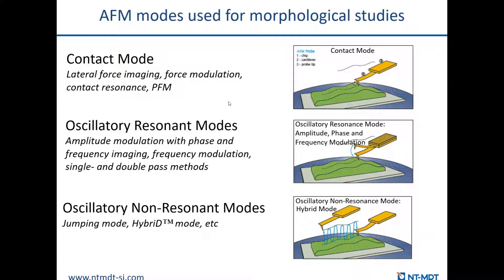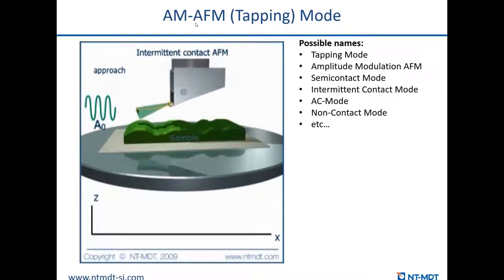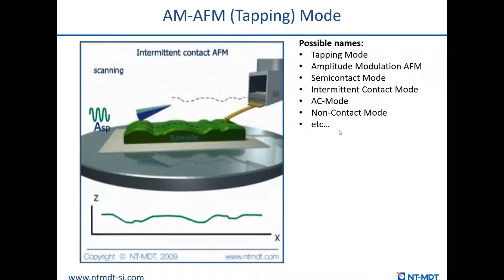There are mainly three ways of keeping interaction between the tip and the sample. First is contact mode. Second is oscillatory resonant mode, or amplitude modulation mode. Third is oscillatory non-resonance mode — we call it hybrid mode. During my talk I will mention all of them. Let's start with AM-AFM, Amplitude Modulated Atomic Force Microscopy. You may have heard other names for this mode: tapping mode, semi-contact mode, amplitude modulated AFM, etc. The principle is the same — we oscillate the cantilever at its resonance frequency mechanically.